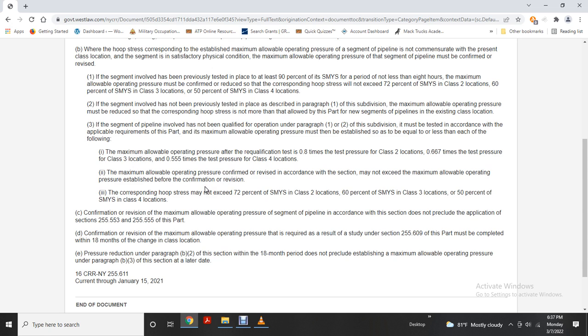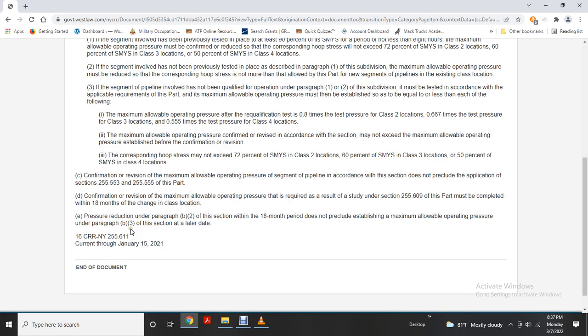Corresponding hoop stress may not exceed 72% of the specified minimum yield strength in Class 2 location, 60% in Class 3 location, 50% in Class 4 location. Confirmation or revision of maximum operating pressure of a segment of pipeline in accordance with the sections is not precluded. The application of 55, 53, and 55.5. Confirmation or revision of maximum operating pressure required and studied under the 255-609 part must be completed within 18 months of the change of class location. Pressure reduction under paragraph B2 of the section within an 18-month period does not preclude establishing maximum operating pressure under paragraph B3 of the section at a later date.